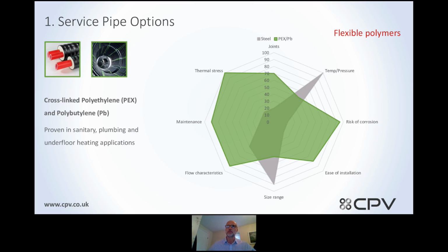Looking at other systems, service pipe options are cross-linked polyethylene and polybutylene, which are flexible polymers. These systems typically will do low temperature, 82 flow and 71 return, for a minimum of 25 to 30 years. They will take higher pressures and temperatures, but just for short bursts. These systems come on coils, so you're reducing your amount of joints. They are polymers, so they're self-compensating. So you don't have to consider thermal stresses, so no anchor blocks or concrete blocks. They're good with chemical resistance against harmful chemicals, and the flow rates are quite smooth, so there's a possibility to reduce your pipework size because the flow rates are a lot better.